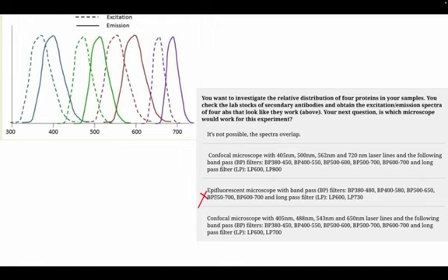excitation. We need 405 to excite this. So 405 is kind of lowest, will excite this fluorophore. 488 for the green fluorophore. This will need somewhere a little under 550. This will need somewhere near 650. So this matches the most appropriate laser lines that will be required for the excitation.